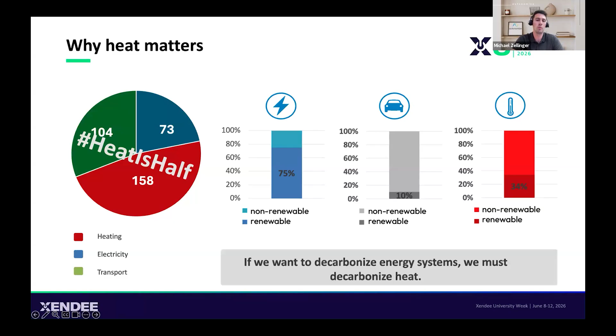This is where solar thermal becomes especially relevant. Solar thermal systems create value where heat demand, temperature level, and available surface area fit together. For lower temperature levels, between 30 and 90 degrees Celsius, 80 to 190 degrees Fahrenheit, solar thermal heat can be used directly as a heat source, for example in domestic hot water systems, for washing, for cleaning, for process water preheating.